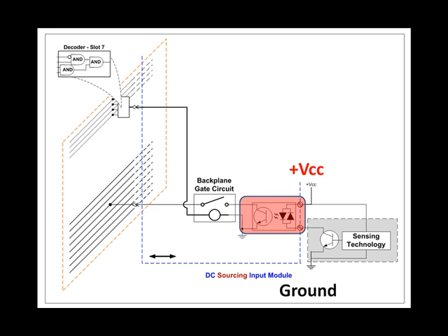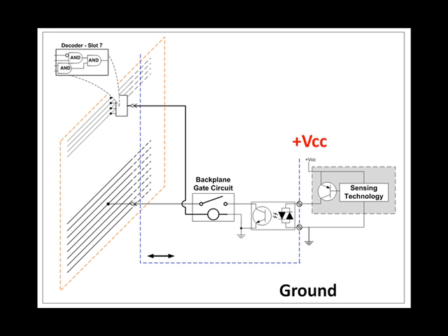In this circuit, the sensor and the input circuit have been swapped around in their relationship with the source and the sink. Again, which of the two is closest to the source? You got it. Pretty simple, huh? And of course, what is left to be the sinking device? Yep, the input circuit of the input module. It is important to point out here that I have used a universal input module that will accept either sinking NPN sensors or sourcing PNP sensors.